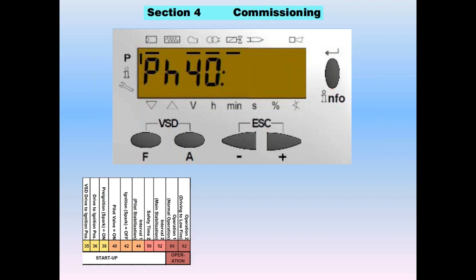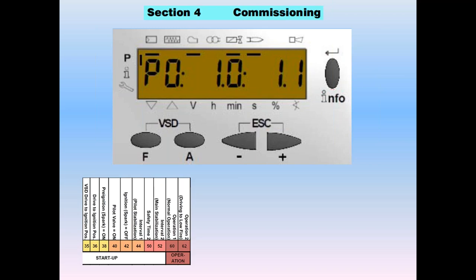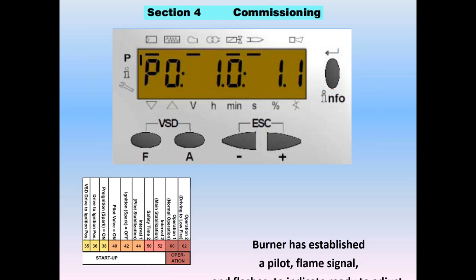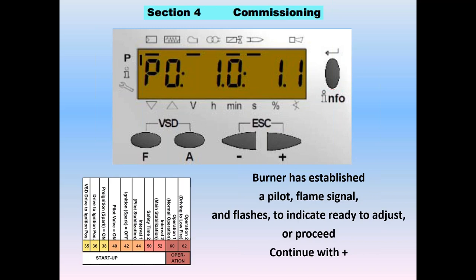It goes into phase 40 — shown by a valve that looks like a bow tie. If phase 40 energizes with the ignition, we'll get a flame signal in phase 42. Then in phase 44, we stabilize the pilot, and the LMV will camp there on the pilot asking how we like the pilot settings. It has established a pilot, has a flame signal, and is flashing P0, indicating it's ready to adjust or proceed with programming.